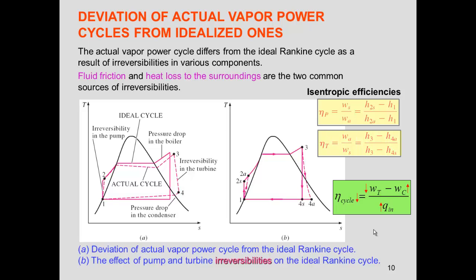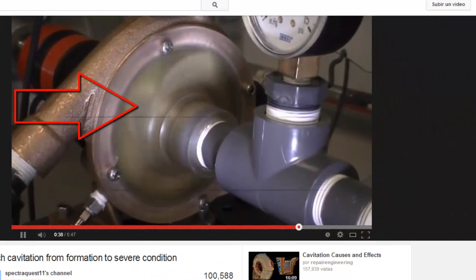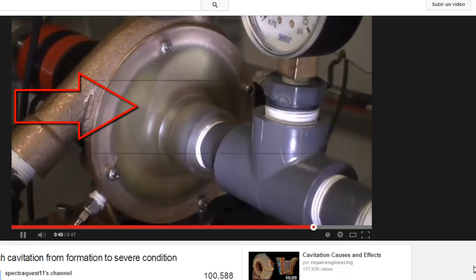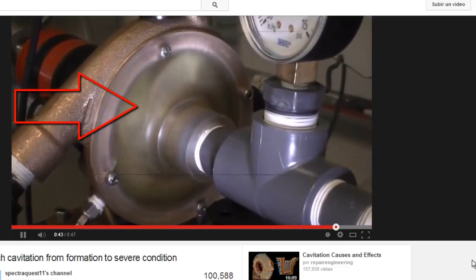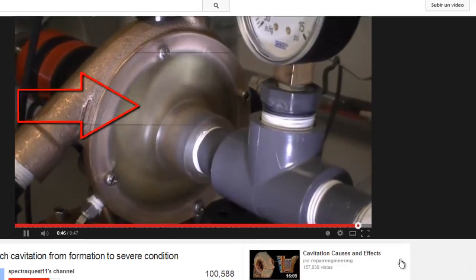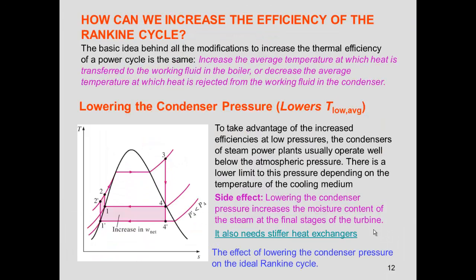In the ideal cycle we assume saturated liquid at the start of the cycle, but in practice we subcool the water slightly. This subcooling is done to avoid cavitation — the sudden change of phase due to pressure fluctuations inside the pump. As shown in this video, cavitation causes the water to boil locally, visible as white areas, and this can cause corrosion damage to the pump.